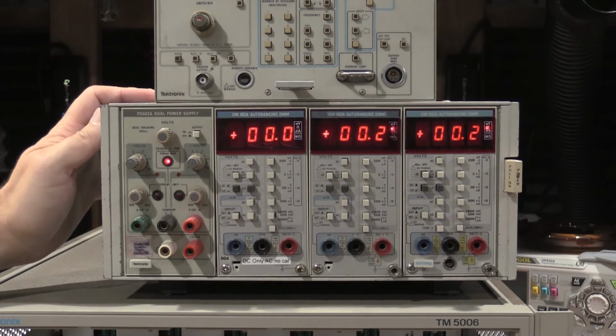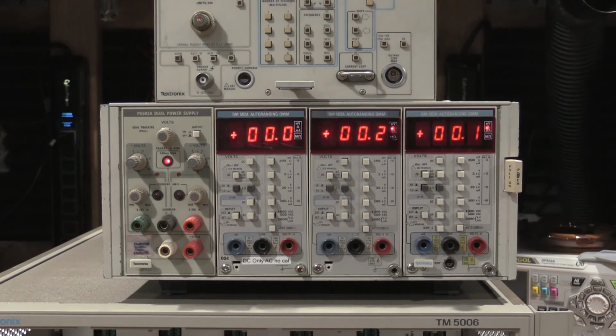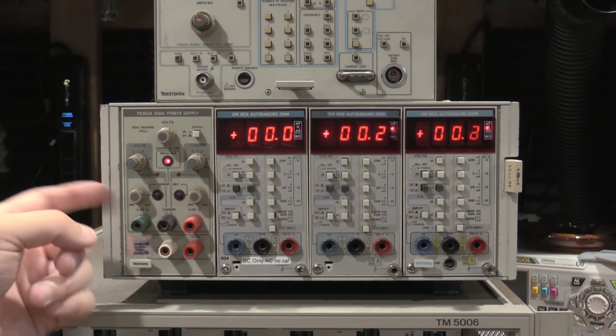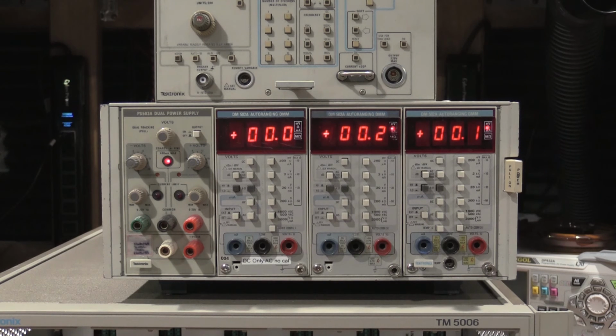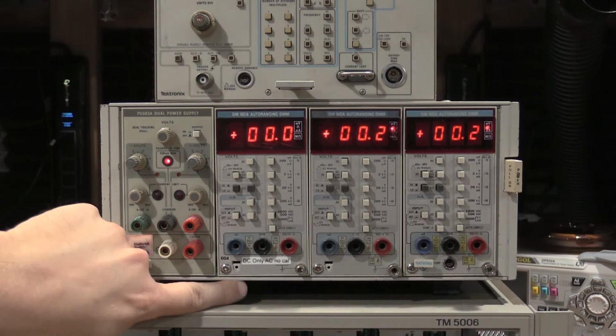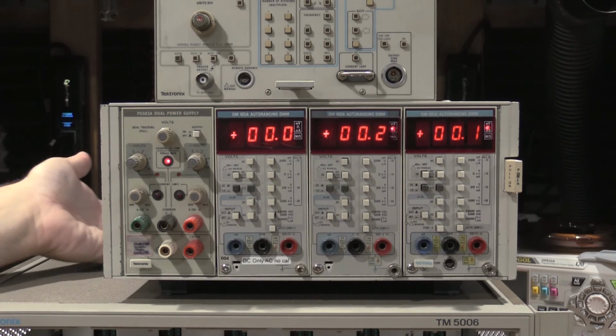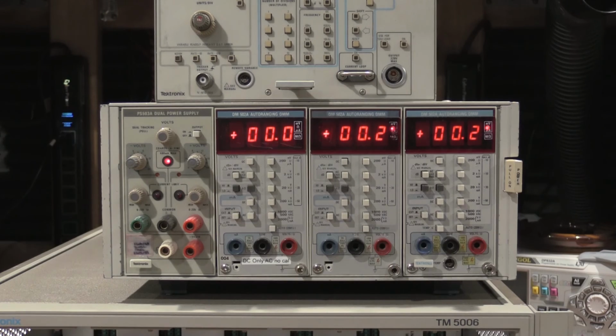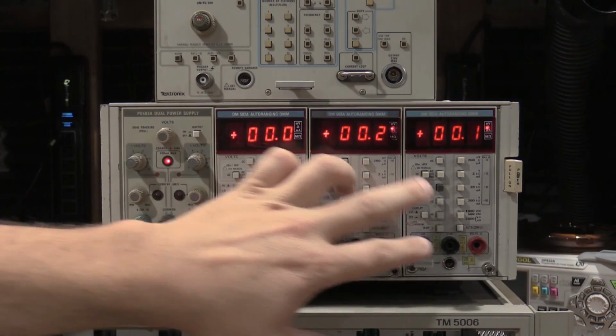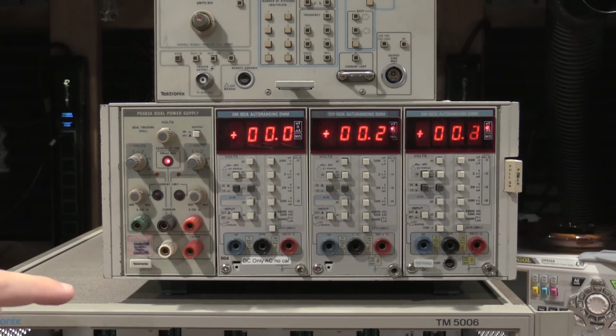The passive cooling on some of these power frames, especially when you pack them full of high power gear, particularly the scope calibration plugins, PG506, TG501, SG503, those types of plugins, they do run very, very warm. That's why I run my calibration plugins in a 5000 series frame for the active cooling. When they were in here, they were starting to get a little overly warm for my taste, but being packed full of meters, the meters don't dissipate that much power, so they don't warm up too much. But it also shouldn't, this is too close on the top right now. This space is large, so air can get in and out the top, and that's the same thing on the other power frame, because I have two of the exact same with 4 meters each, and they breathe just fine that way.